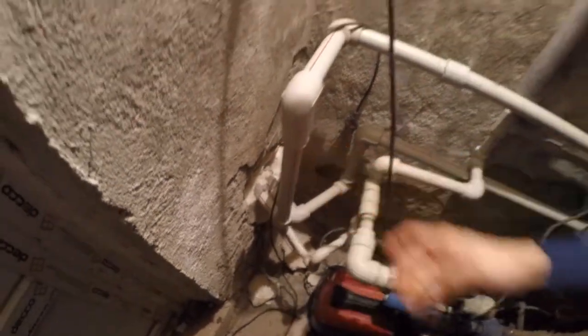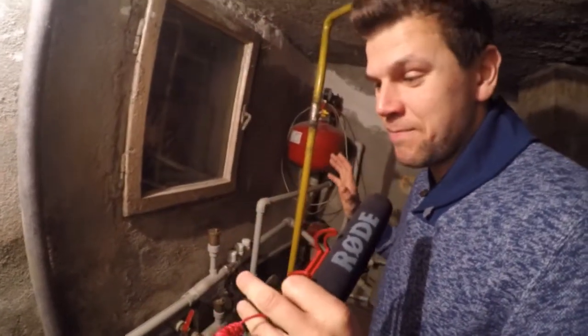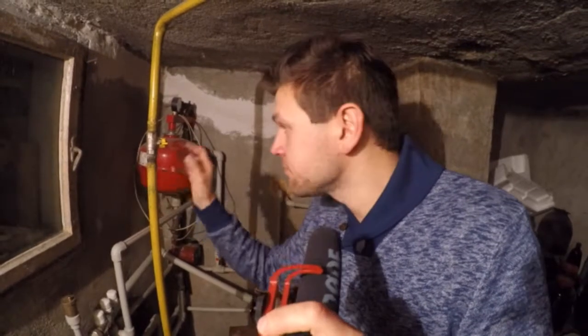This boiler is gas fired. It is the original one and it is still used — when is it used? Let's go take a look. Okay, welcome. We're in the second boiler room of this fantastic house. Starting at the exterior wall, our supply and return pipes come out the wall. They are buried underground, they are insulated. They're coming from the wood burning boiler into here, because this is the first mechanical room that came with the house. This existing boiler is a gas fired unit. The whole purpose of the conversion to wood was to eliminate the use of natural gas because of the very high gas prices here. This boiler will only be turned on during emergency use. It does operate still, it's still functional, but the gas valve is shut off right over here.